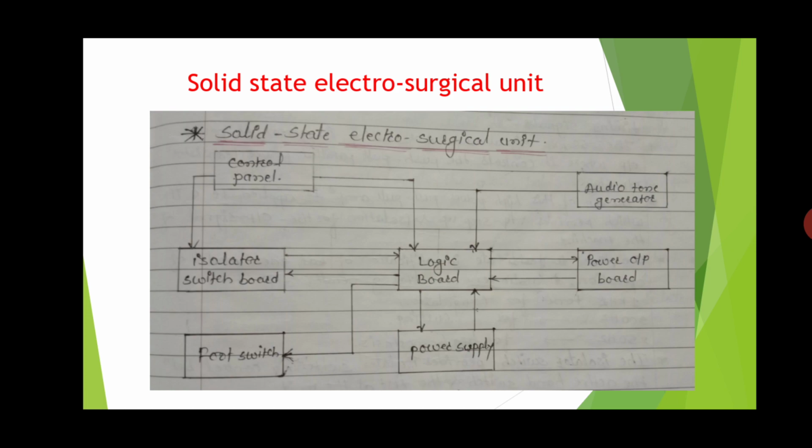The logic circuit gives information from the foot switch, finger switch, and the alarm sensing points. The thermostat is sometimes mounted on the power amplifier heatsink. If the temperature is more, then it becomes an open circuit signal, triggers the alarm, and interrupts the output.